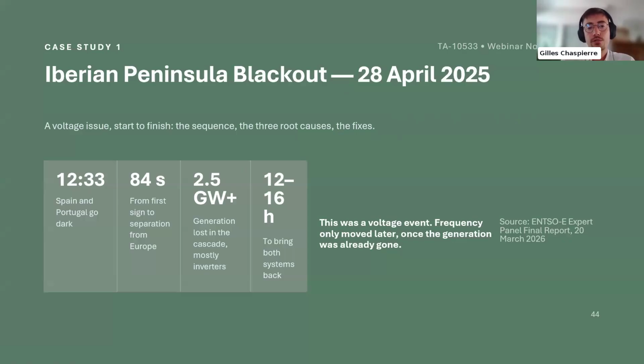Two main messages on this slide. First, it's the worst European blackout in 20 years. Why do we say worst? It's not specifically linked to the amount of lost power. It's more linked to the time it took to go entirely black. Only 84 seconds, less than 2 minutes, complete blackout. And the third message, the most important one, it was a voltage event, meaning the root cause of this blackout is a voltage issue, an overvoltage issue as you will see, not a frequency or inertia issue. Frequency is the consequence of the voltage issue. Yes, we can go to the next slide.